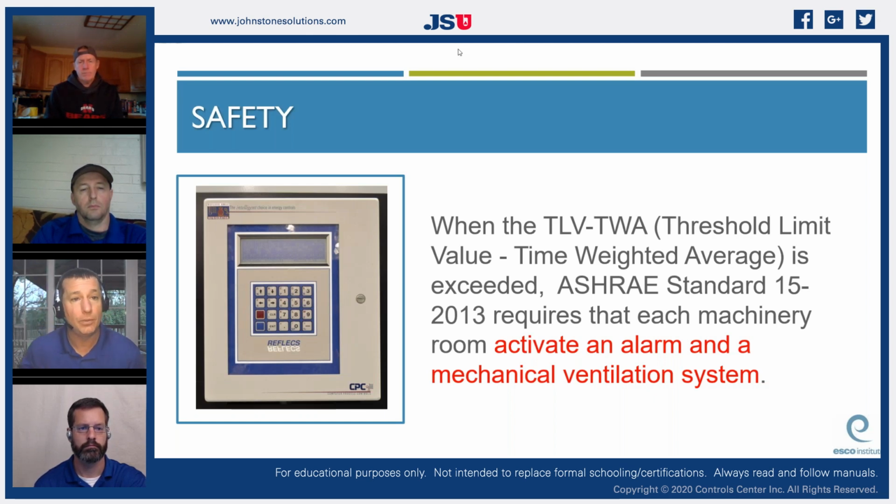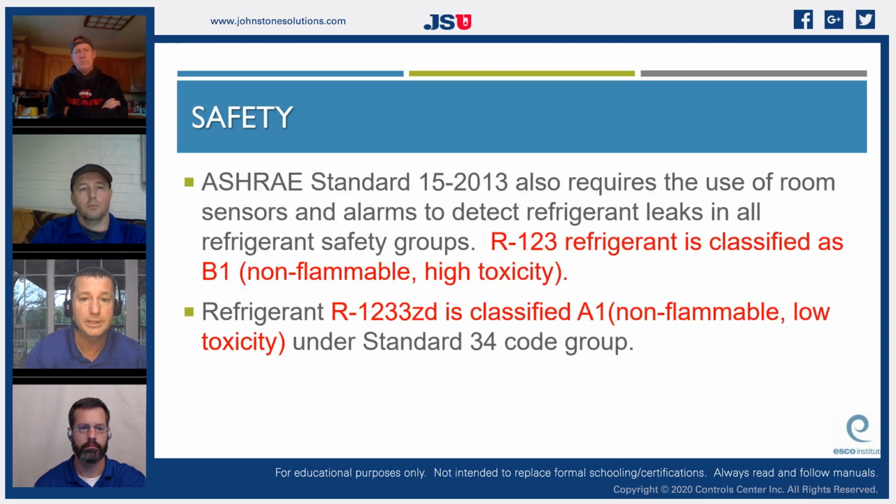So if you drive around the backside of pretty much every large grocery store here in the United States, you're going to notice a wall with a bunch of mesh filtering on it. That is your incoming air, and they have mechanical louvers on the inside. And then right above that, you're going to have exhaust fans on the roof. So the machine rooms are monitoring refrigerant leaks because if I have a compressor blowout or condenser blowout or evaporator blowout, that's where my refrigerant is going to be, in that machine room.